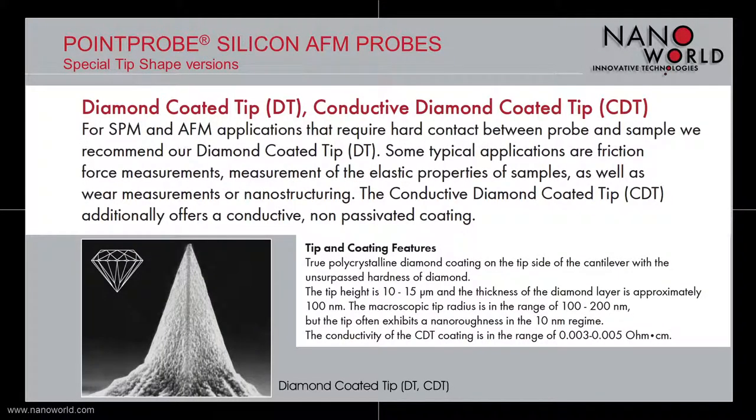The third special tip shape versions are the diamond coated and conductive diamond coated tips. These tips are used for applications that require hard contact between probe and sample. Additionally, the conductive diamond coated tip offers a conductive, non-passivated coating. The tips are 10 to 15 micrometers high and coated with a true polycrystalline diamond coating on the tip side of the cantilever. The thickness of the diamond layer is approximately 100 nm. The macroscopic tip radius is between 100 and 200 nm, but the tips often exhibit a nanoroughness in the 10 nm regime. The conductivity of the conductive diamond coated tip is in the range of 0.003 to 0.005 ohm centimeters.